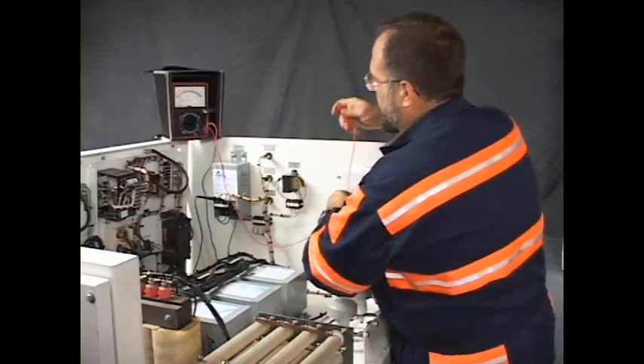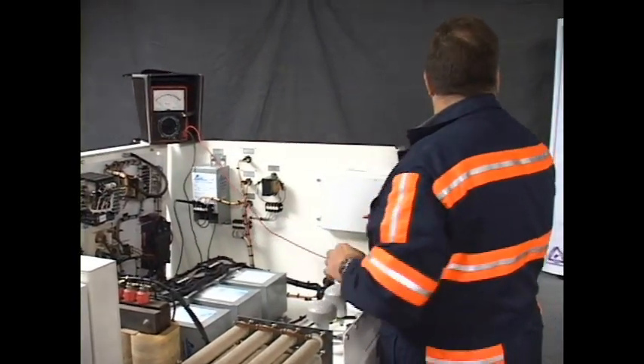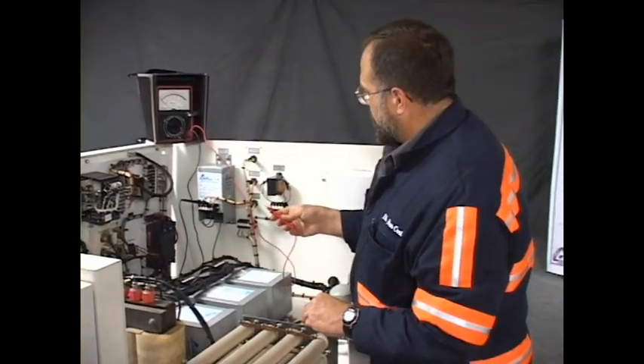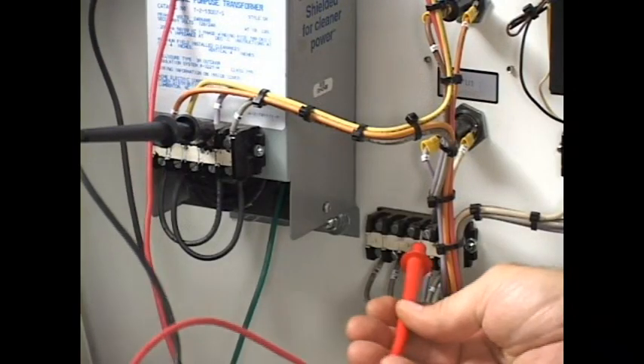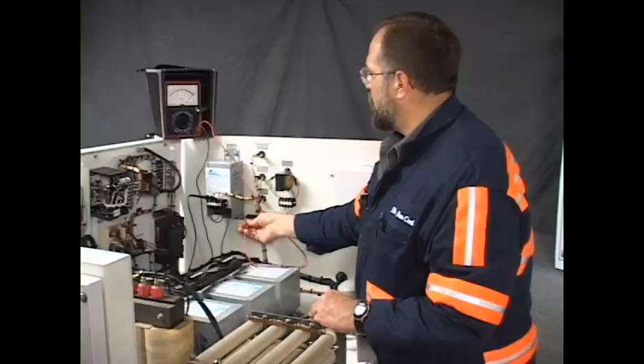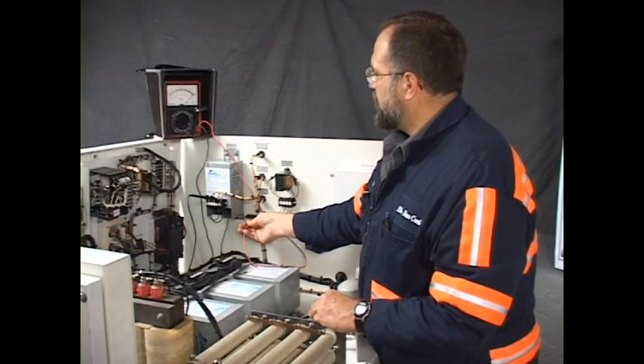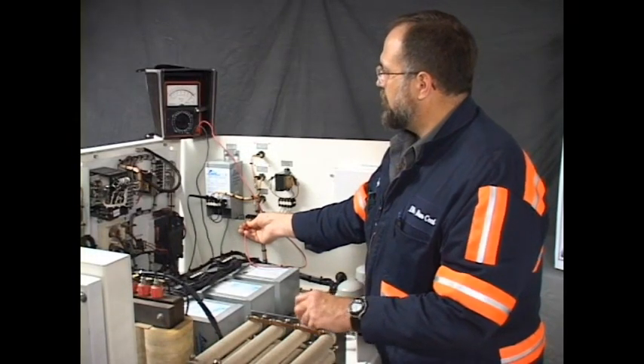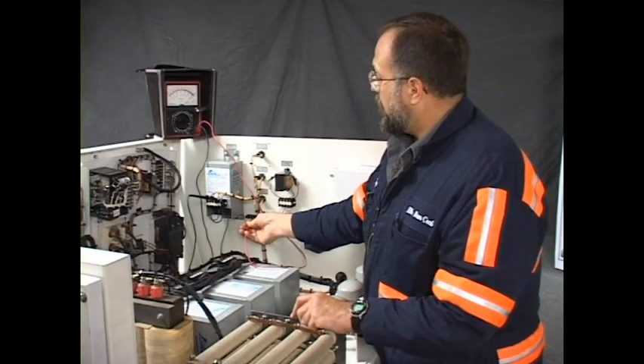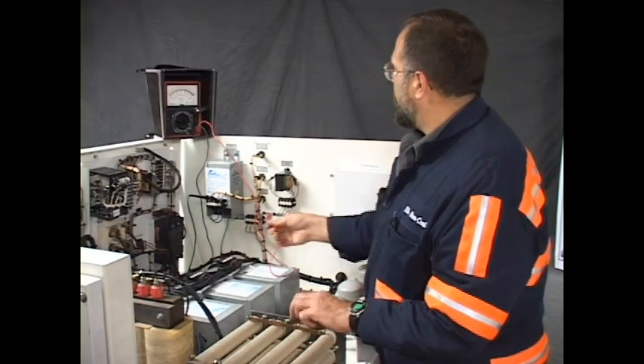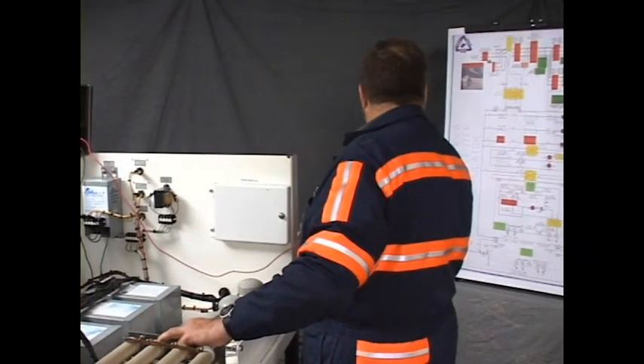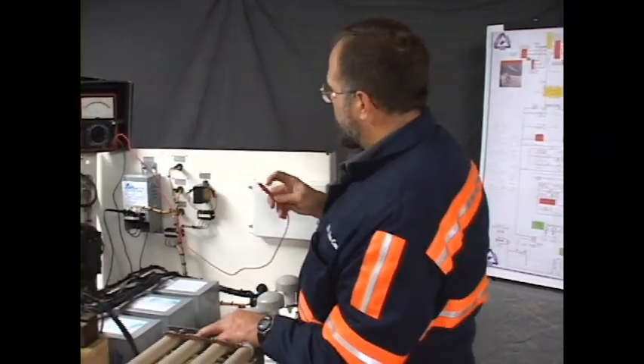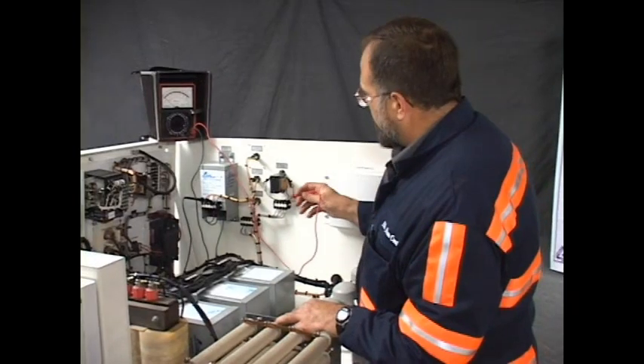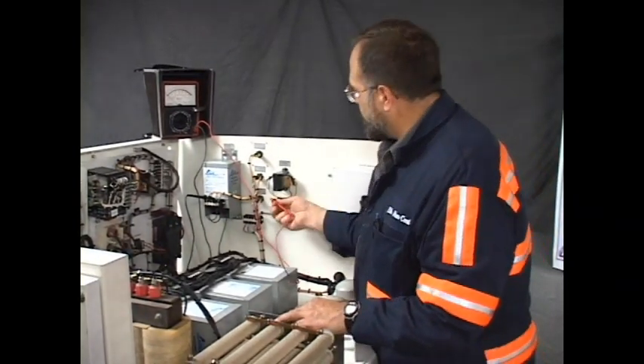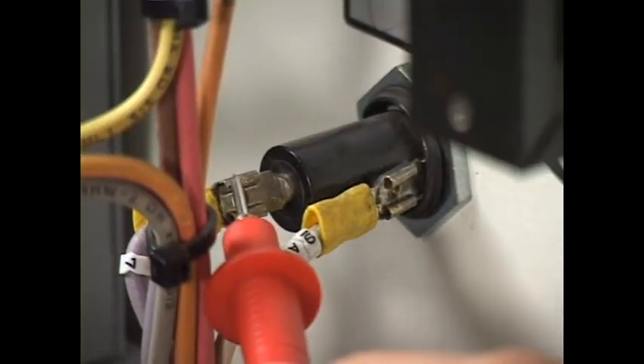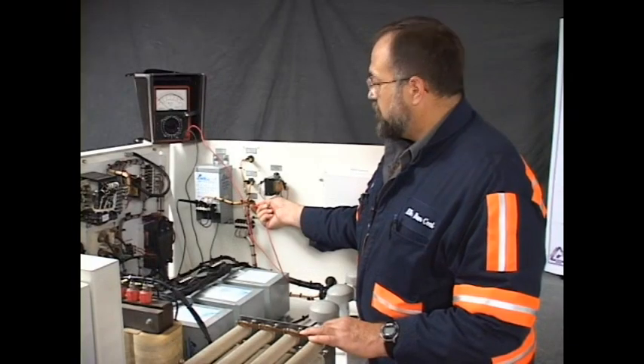Okay, I'm going to attach one lead. And the first point on the drawing that wire 7 goes to is here, to a terminal board. And as you notice, the meter sweeping all the way to the right indicates no resistance. That wire is intact. From wire number 7 going to the terminal board, it then goes to the fuse, the secondary fuse, labeled as FU1. It's a 5 amp fuse. Again, the line side of this type fuse mount is usually directly in the rear.